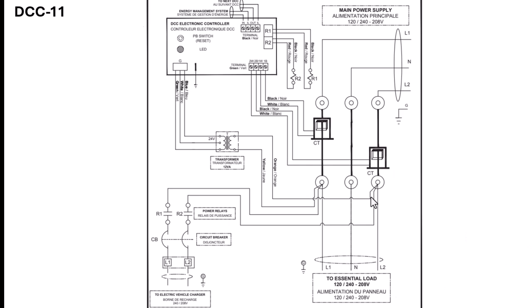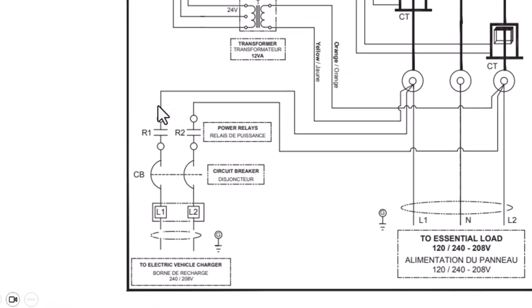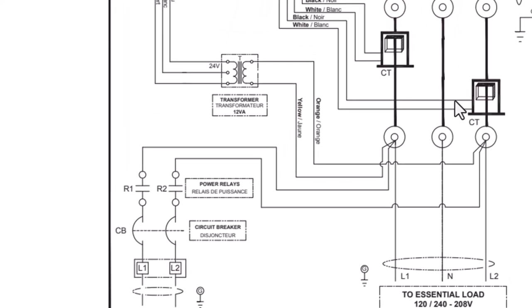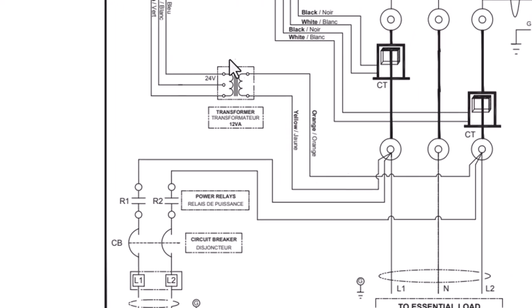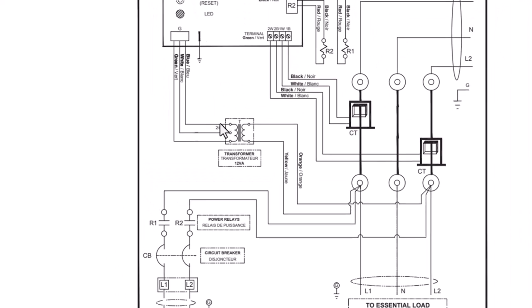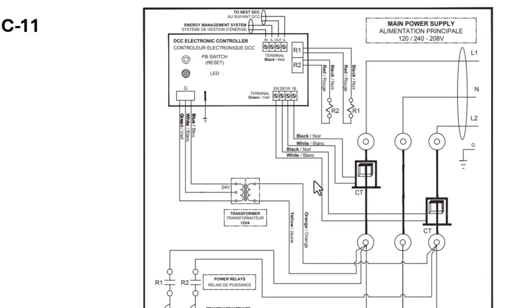And then within the box, you could see that it splits off, and one goes basically to your power relays here, which will basically open and close the circuit to your EV charger. And then some of the power from the main goes into a transformer that basically converts the voltage to a low voltage for your control wiring. And then your CT basically takes the amp reading and sends it to the circuit board where the amperage is read.